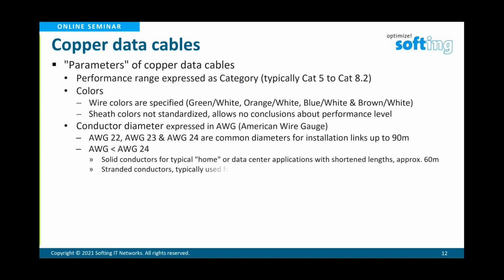The conductor diameters are expressed in American Wire Gauge, AWG, and the typical cables today are AWG 22, 23, and 24, commonly used for links up to 90 meters. Especially for longer runs allowed in the ISO IEC standard, you may prefer a cable with a larger diameter. The smaller the AWG number, the thicker the conductors are, and for AWG numbers less than 24, you have solid conductors typically for home or data center applications with shortened length.